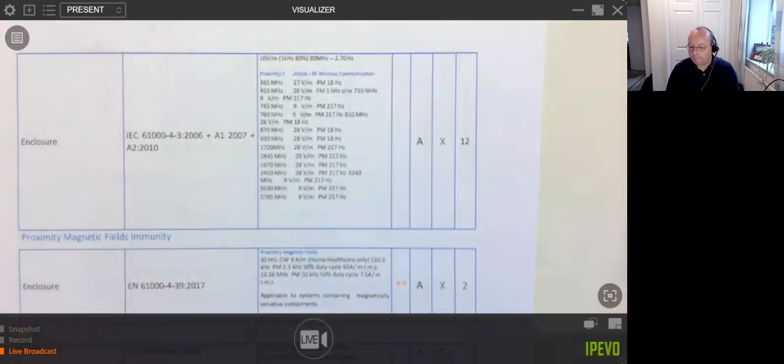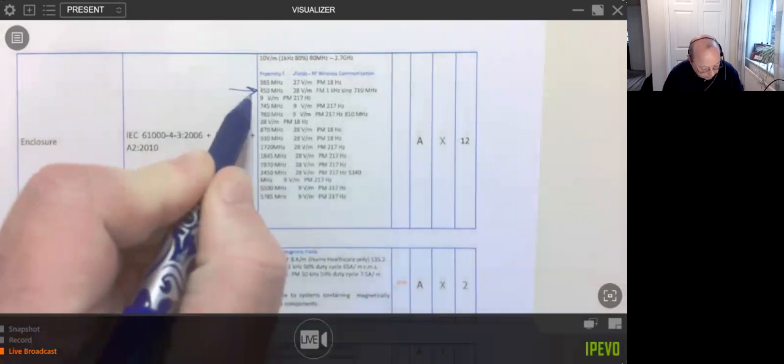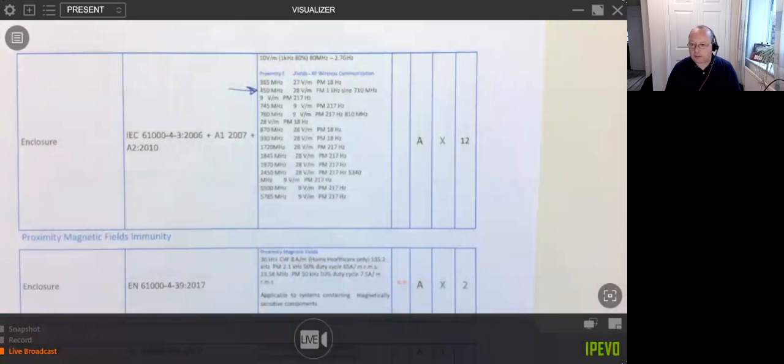respond to them. For example, this week and last week I've been testing a medical device with temperature. Everything was great until we did the spot frequencies, and at 450 megahertz, suddenly the temperature started going wild. And when we came off it, it was actually a band, about 440 to 480 we've discovered. But the standard's interested in 450. It suddenly went absolutely crackers.